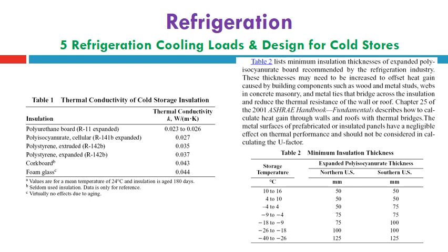These thicknesses may need to be increased to offset heat gain caused by building components such as wood and metal studs, webs in concrete masonry, and metal ties that bridge across the insulation and reduce thermal resistance of the wall or roof. Chapter 25 of the 2001 ASHRAE Handbook Fundamentals describes how to calculate the heat gain through walls and roofs with thermal bridges. The metal surfaces of prefabricated or insulated panels have negligible effect on thermal performance and should not be considered in calculating the U factors.